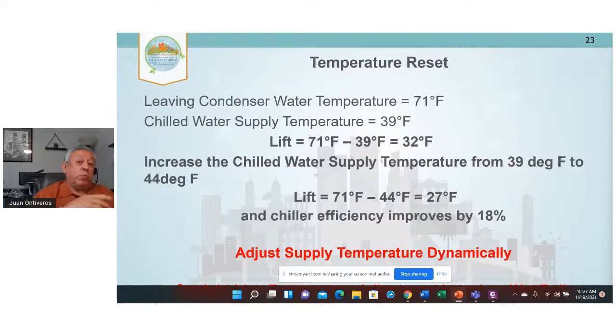The way we did it is we put in a straight line adjustment in our control scheme based on wet bulb. If it's really humid, I've got to get more cold water out to the buildings because I'm extracting humidity. It's very humid here in Austin. If it's winter or drier, I don't have to send as much chill water. I can adjust the chill water temperature up. So again, I want to reduce that lift.